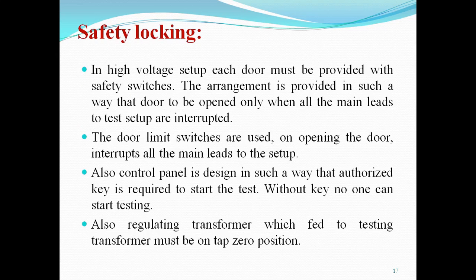Safety locking. In a high voltage setup, each door must be provided with safety switches. The arrangement is such that the door can be opened only when all the main leads to the test setup are interrupted. So you will find that this kind of interlock is provided in the high voltage laboratory. The door limit switches are used so that opening the door interrupts all the main leads to the setup. Once the door is open, the main transformer and high voltage test equipment are automatically disconnected from the main supply. Also, the control panel is designed in such a way that an authorized key is required to start the test. Without the key, no one can start testing.